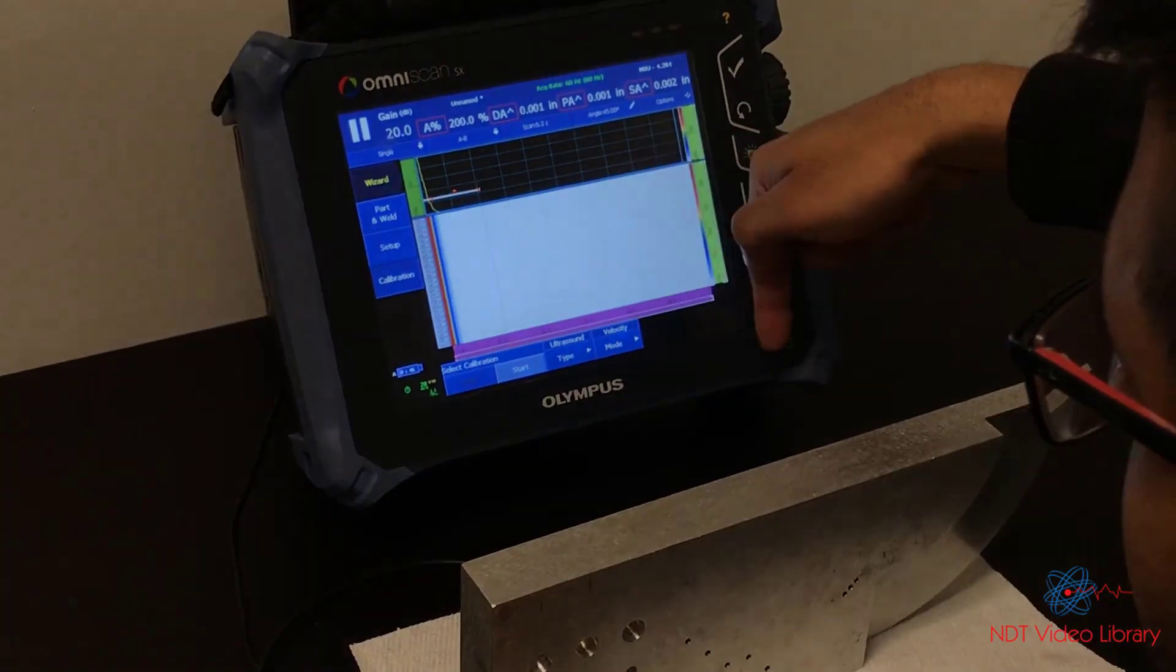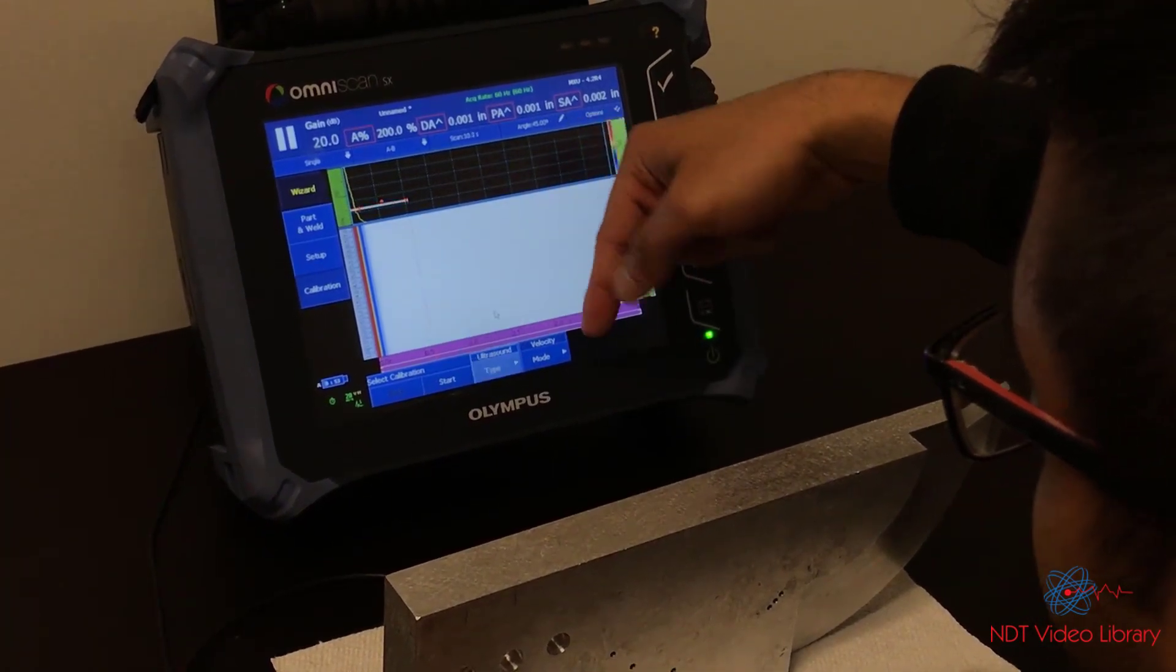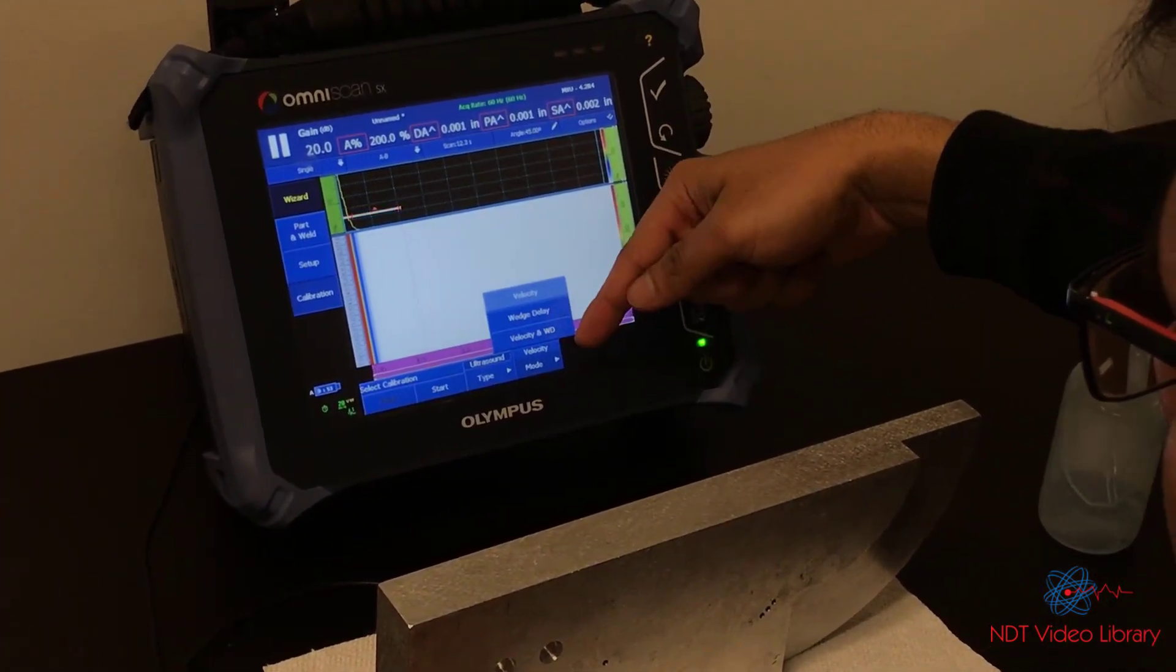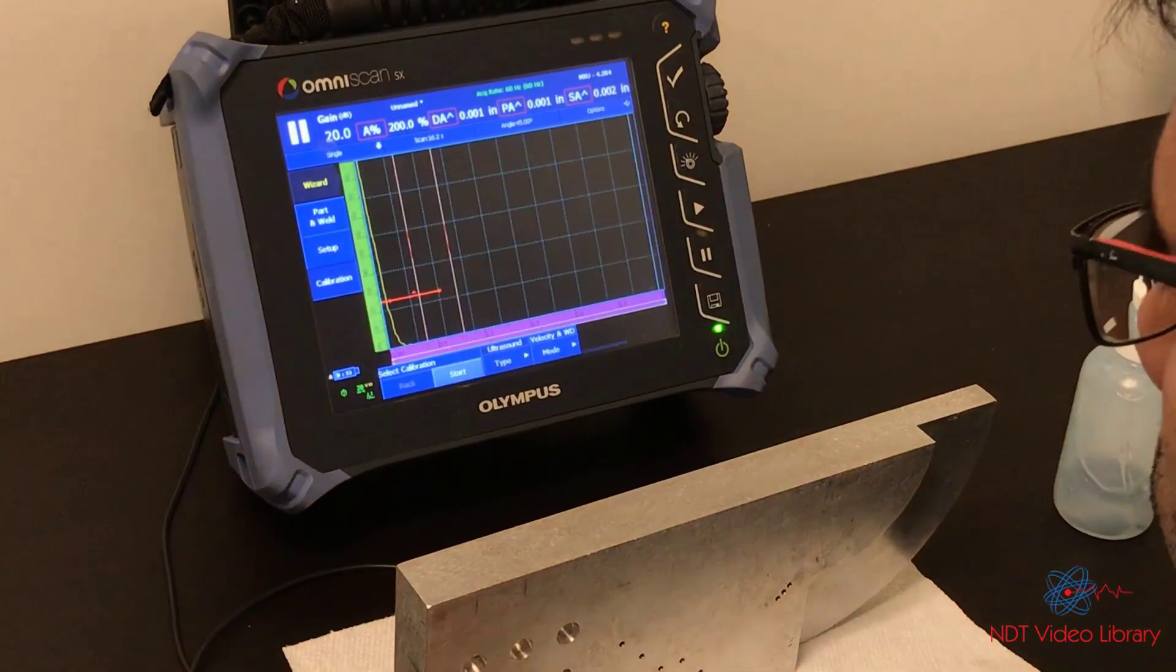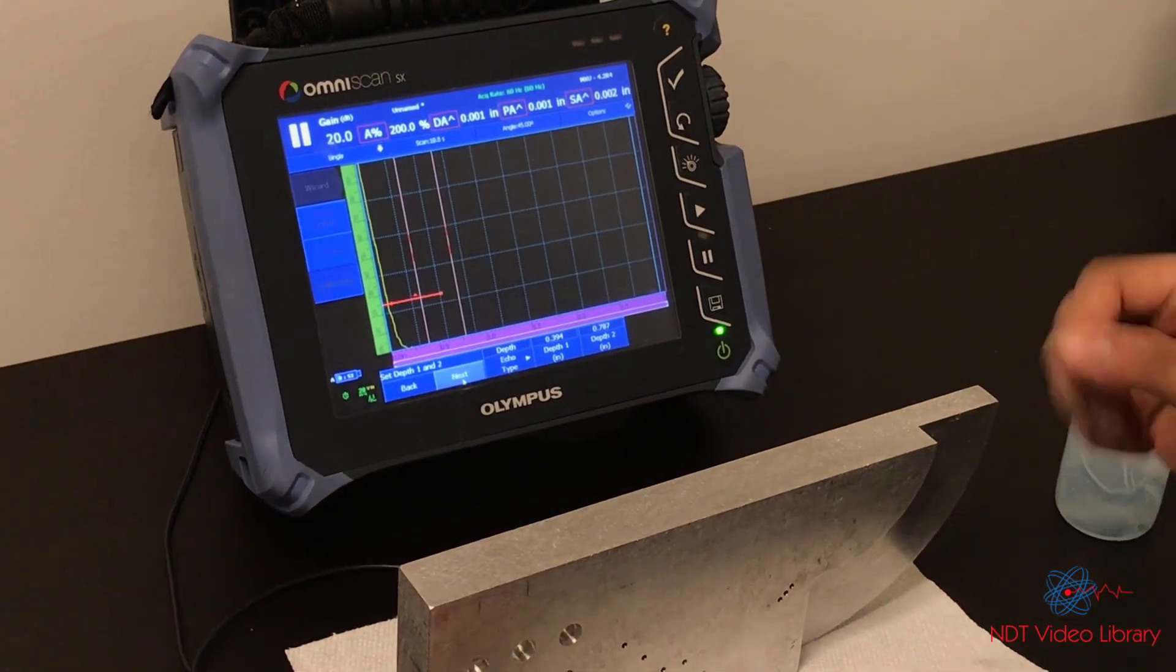Remember, we always go from top to down, left to right. So we move to calibration. Type ultrasound. Mode, we can calibrate both together, velocity and wedge delay together. Start.